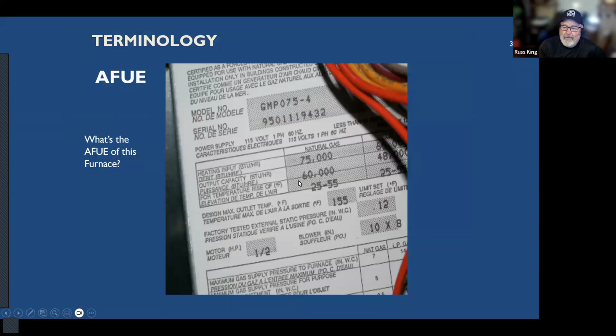So if you've got 60,000, you're putting in 75,000. You've got to take the cover off the furnace, and sometimes it's on the inside of the cover. Sometimes it's stuck on a fan or something, or on a piece of metal on the inside. Okay. Here's the model number, the GMP 075. So that's telling you what the input of the furnace is. So you're putting in 75,000 BTUs worth of gas, but you're only getting 60,000 out of it. All right.